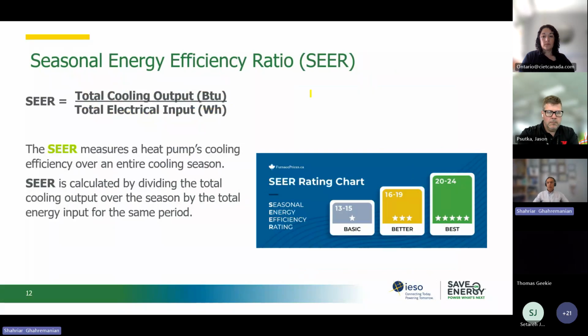The other seasonal efficiency factor is the seasonal energy efficiency ratio. Again, this one deals with the total cooling that is needed or output to the building, divided by the total electrical input to the building. This is again seasonal, which means that it considers the entire season of operation. So again, we have a SEER of 13 to 15, and then it can go up to 20 to 24, which are the best to be considered.